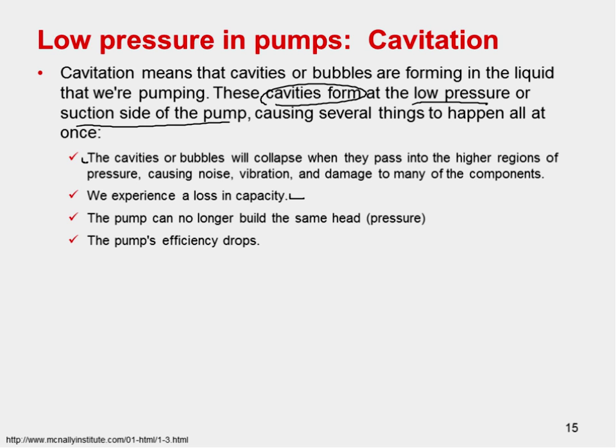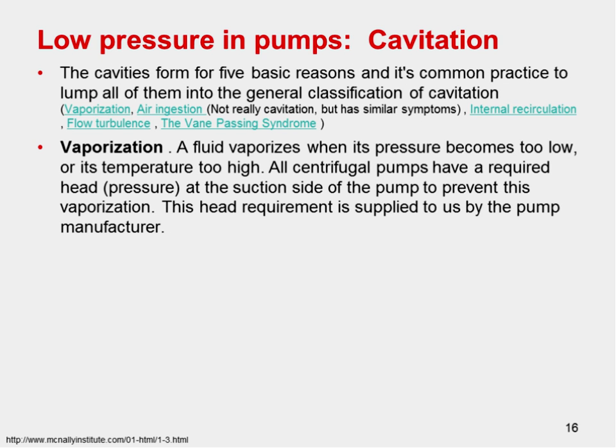So that will result in a loss of capacity. You cannot build the same pressure, and the pump's efficiency drops. Also, the pump will not last as long. So remember, those little bubbles form on the suction side, and when they collapse on the higher pressure side, it's really, really bad, and it also makes a lot of noise. It's like the pump is gurgling, and I will post some videos that show this gurgling noise of a pump. It's a very typical noise that they make.